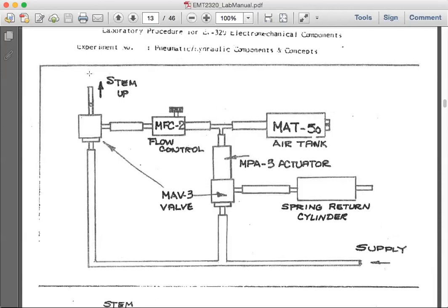So when you had the second stage, when you activate the stem of three-way valve, flow control did not control pressure entering the system. So the pressure entered the system quickly, and the moment you press the stem, the moment the pressure activates the actuator, piston shoots out instantaneously.